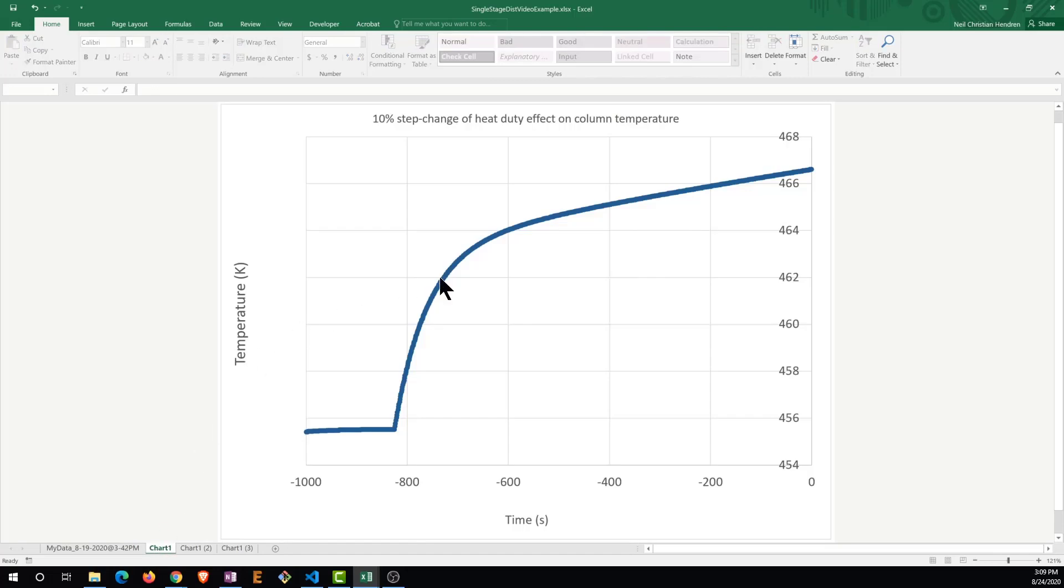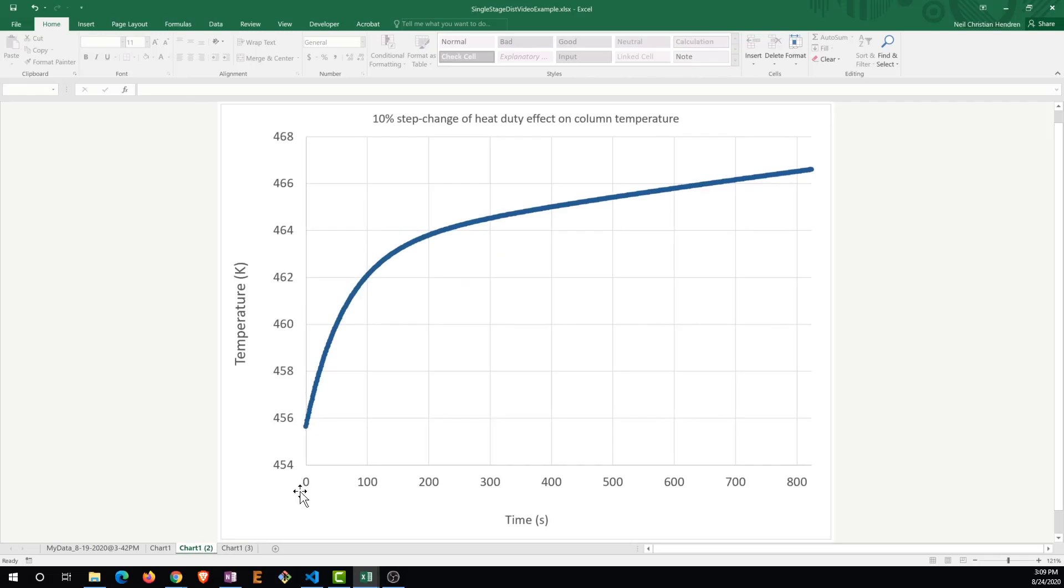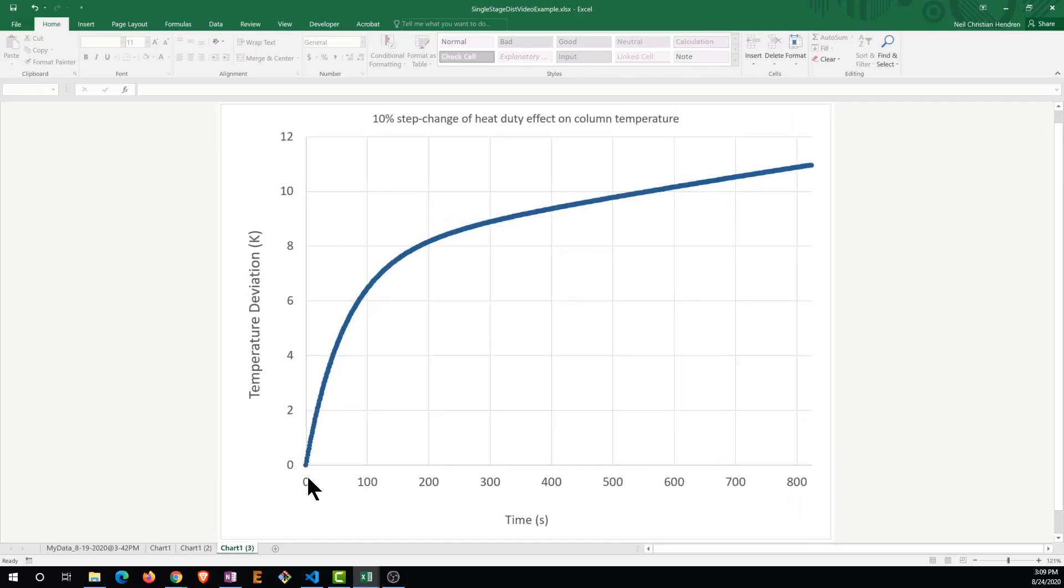Here I have plotted the data in Excel and I have created a plot of the step response. Next we will want to trim the data so that the step change input occurs at t equals zero. Then we will want to convert the process variables to deviation form such that the temperature is zero at t equals zero.